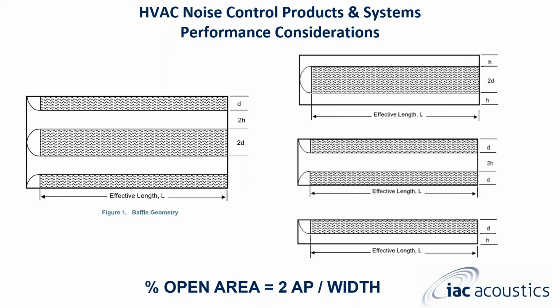Now let's look at percent of open area. This is calculated as 2 AP divided by width. Please note here that half the gaps and half baffle thicknesses are H and D respectively, and performance is based on these parameters. Now, take a look at the single silencer on the left of the screen. Now look at the 3 on the right, all having a different configuration. All have the same acoustical performance as the one on the left, assuming H, D, and L are the same.